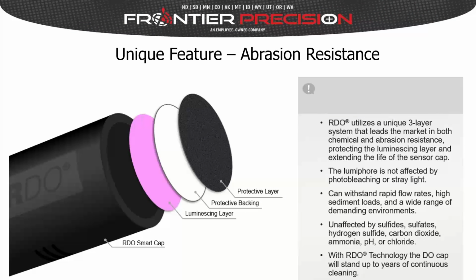Another unique feature is the abrasion resistance of our cap. So this slide kind of shows a 3-layer cutaway of that foil or that luminescing sensing material, where on the very top you have a protective layer, behind that you have a protective backing, and then you have the luminescing layer underneath that basically reflects that red light back to the sensing diode. So this 3-layer system leads the market in both chemical and abrasion resistance. And importantly, if you're working in shallow water where you have bright sunlight on there, there's no effect from photo bleaching or inaccuracy from stray light on those sensors.